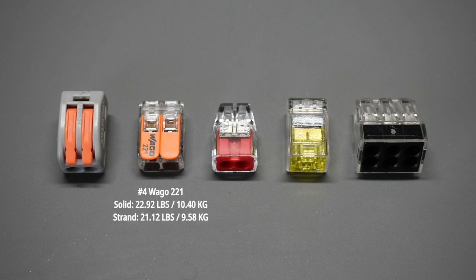In fourth place we have the Wago 221. And you can see the pull-out force for solid and stranded is very similar and much lower than the push-in type.